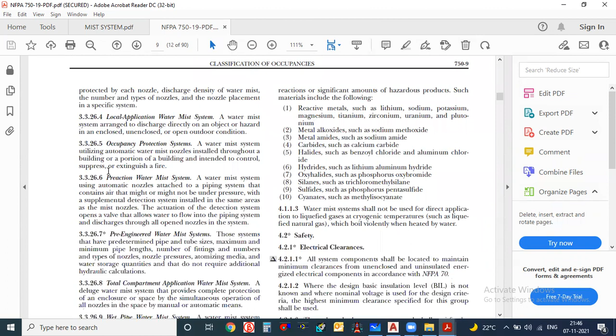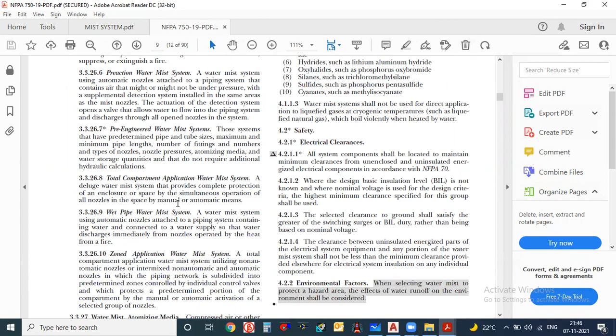Engineered water mist systems can include local application, pre-action, even pre-engineered water mist systems can be used here. Wet pipe water mist system can also be applied. This is like the general wet sprinkler system - that's how the wet pipe water mist system works.